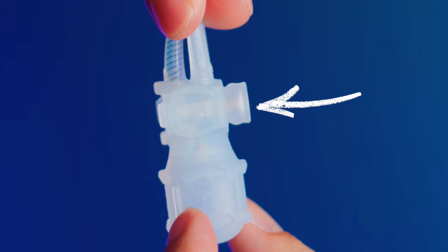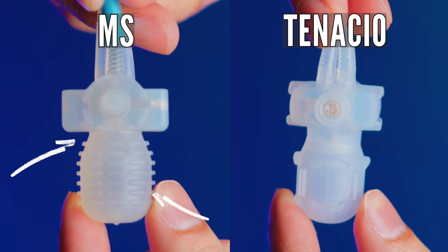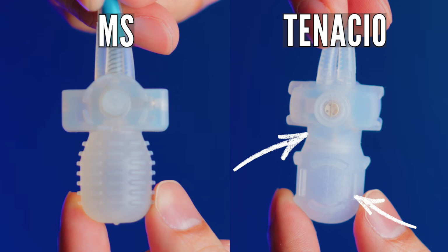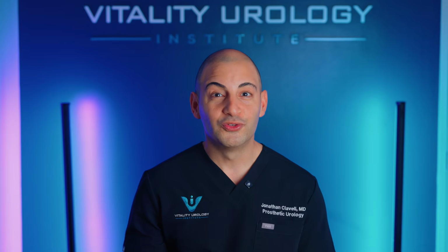The Tenacio pump is intended to be pressed once and released for deflation, and it has a click-like feedback that is very subtle. The MS pump has a smaller neck and slightly larger bulb for inflation. On the other hand, the Tenacio pump has a longer neck and a slightly smaller and supposedly more efficient bulb. The user does need to understand that sometimes pressing on the neck may not push in as much fluid, and sometimes it is better to inflate from the bottom of the bulb.